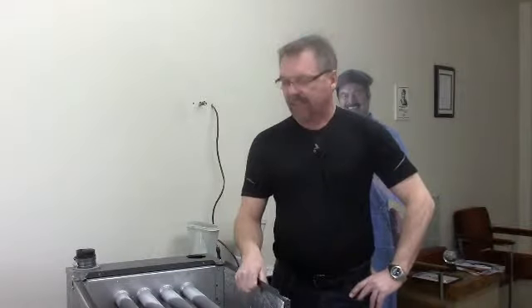So now that you've seen what can happen to a heat exchanger or to your furnace in general, you know again why airflow is so important. For instance, most people have just a 1-inch air filter in their house. Marketing tends to fool customers into believing that "good up to 3 months" means they don't have to change their furnace filter for 3 months, and that they only have to change it 4 times a year. Well, that is in ideal situations. Most people are not living in those ideal situations with clean ductwork, and we're generating dirt, whether it's through pets or kids creating dirt and dust in the house. So when you have a restrictive air filter, you're going to have problems.